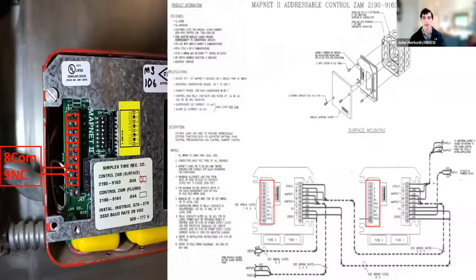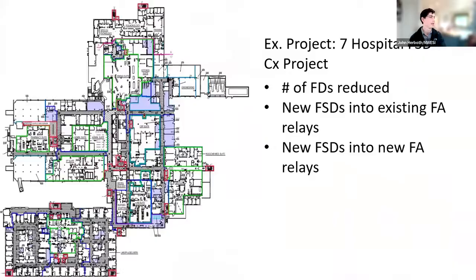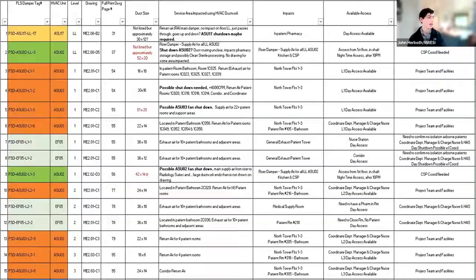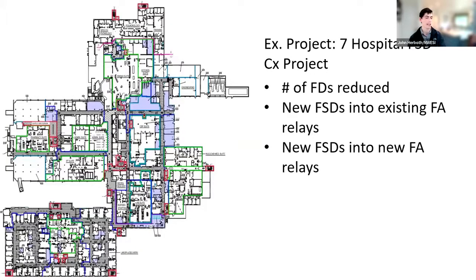Importance of fail safe. You need to fail closed for most circumstances, unless it's smoke control. Those are very important, and you need people with technical capabilities to do them. And then you can run into hospitals where they are reviewing the fire smoke dampers, and you want to make sure that they operate correctly by zone, and any changes in zoning for smoke compartmentalization. But in a lot of active hospitals, you can't do that. You can't test and start smoking heads because it's an operating hospital. So we work with a fire alarm provider to trip relays instead and physically trip them, so that we can test the integration part.